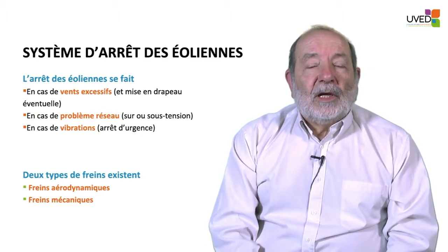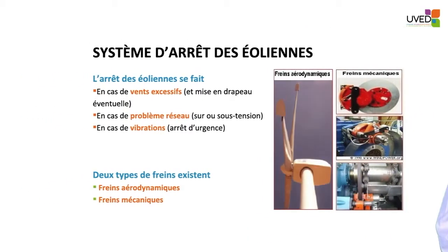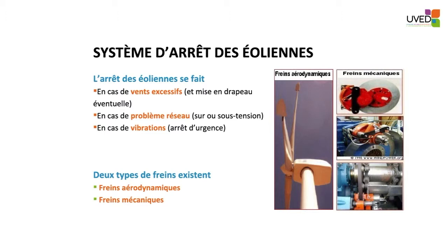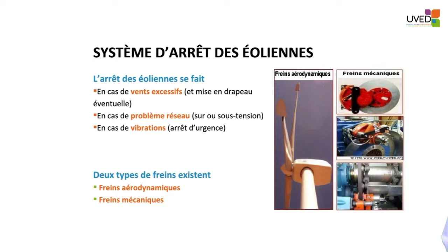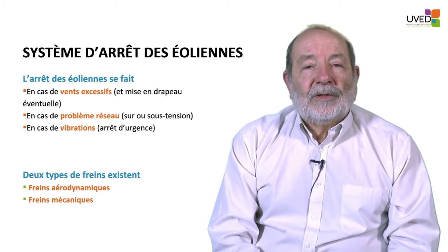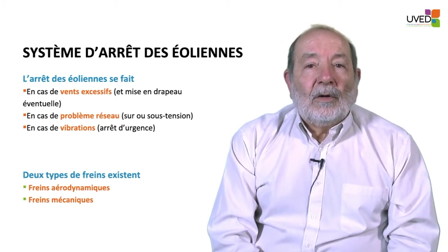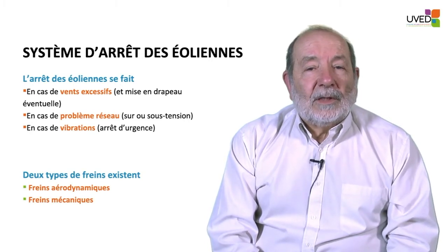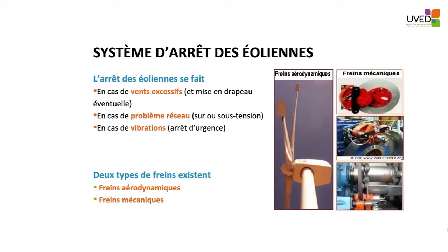There are two types of braking systems. If a large rotor is rotating, it cannot be slowed down with mechanical brakes, so aerodynamic brakes are used. The blade will swing, and by increasing the pitch angle to 90 degrees, the rotor slows down. At 90 degrees, the blades are feathered and the windmill stops.